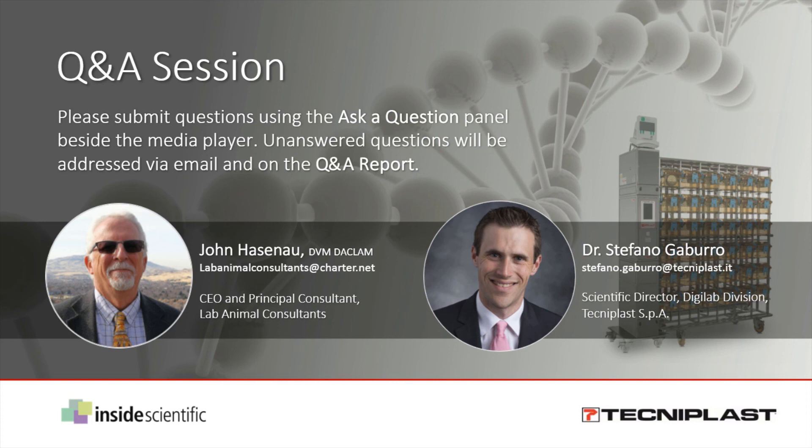Here's a question from Christina: can the IVC or DVC cage systems be integrated with partner technologies, for example DSI telemetry? Having previously worked for DSI, we did some tests on normal IVC with blood pressure devices using single-cage animals and didn't see any interaction. We don't suspect any interaction with transmitters measuring temperature, blood pressure, or ECG, as those have very high amplitude signals. However, we do need to test with each specific transmitter type. Short answer: we are currently testing it, and more tests need to be done.